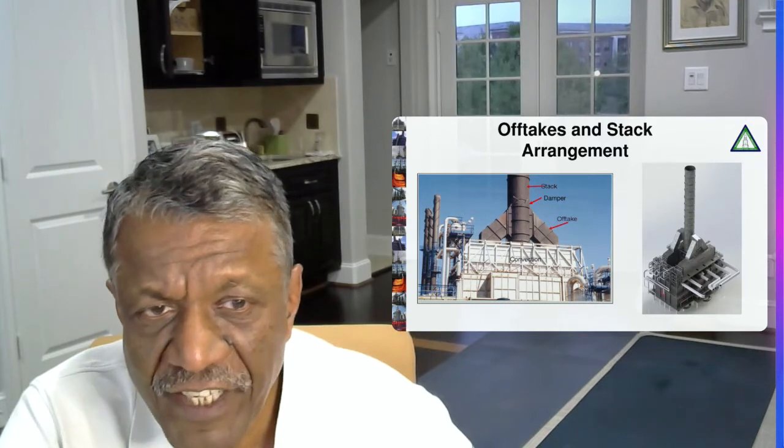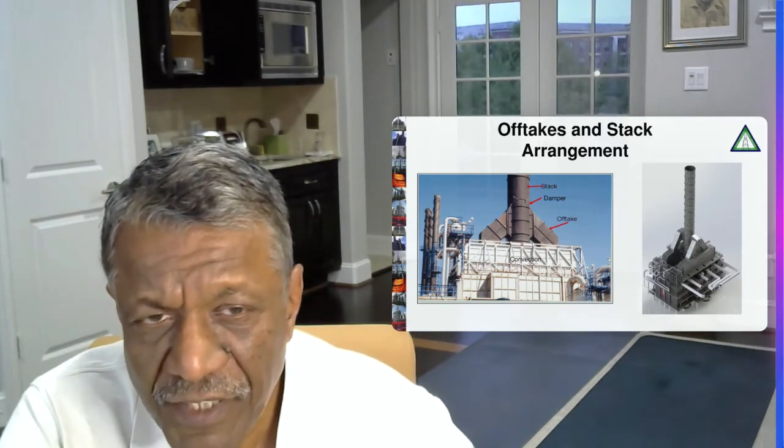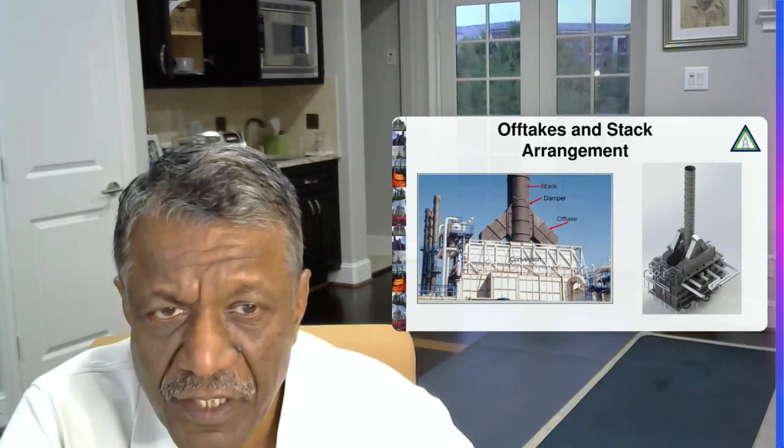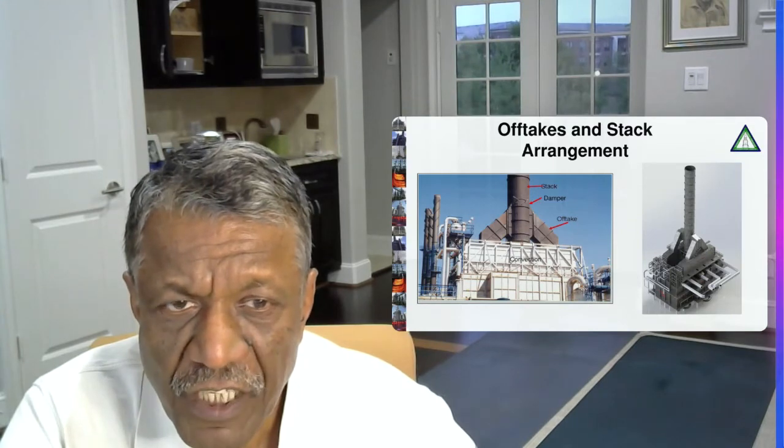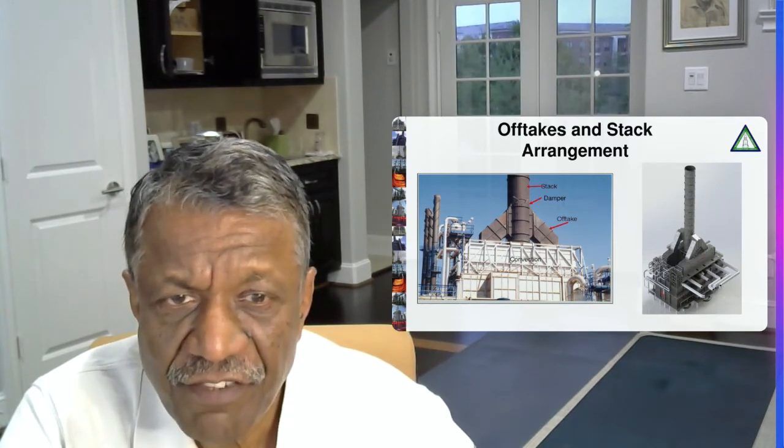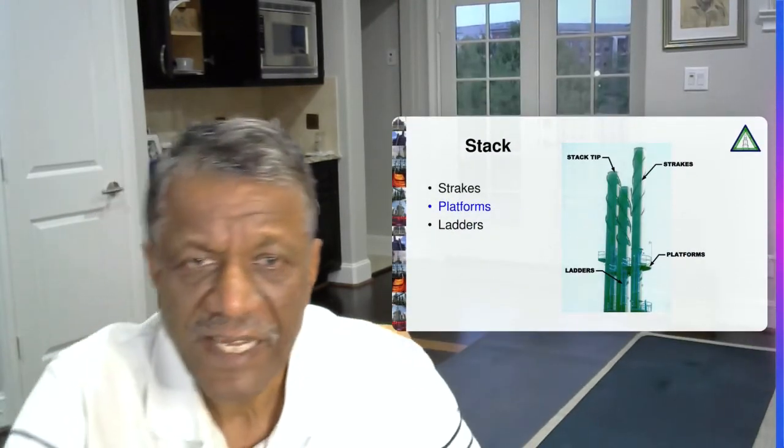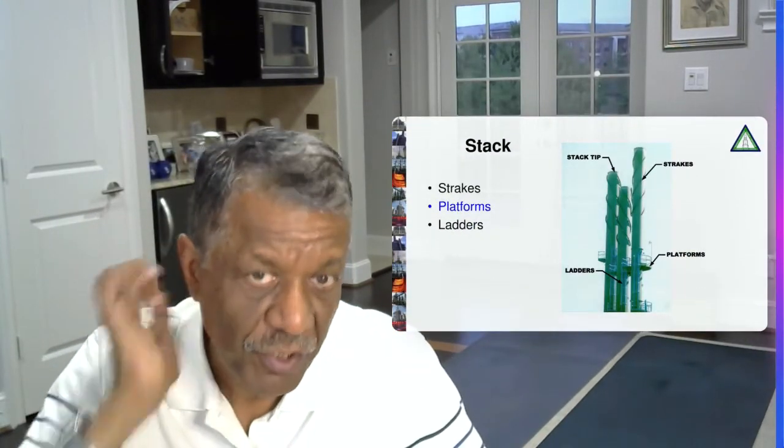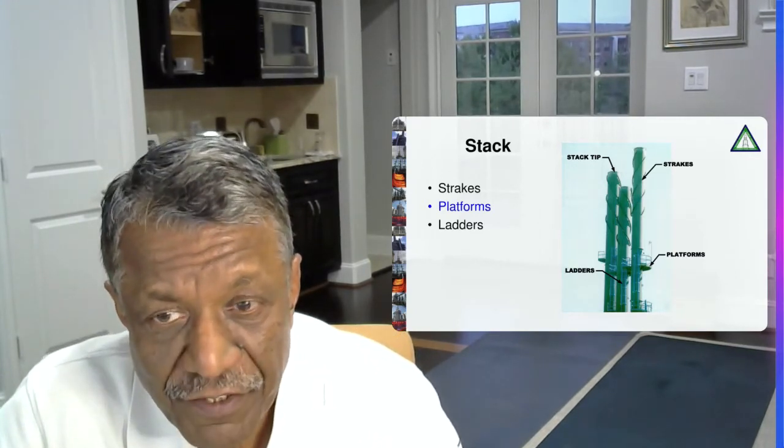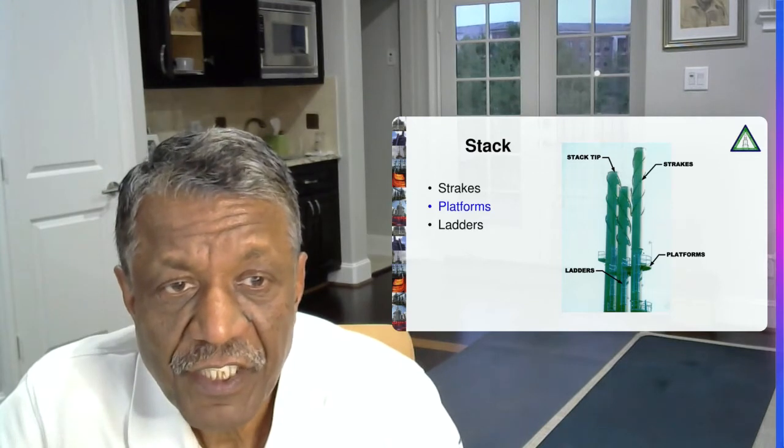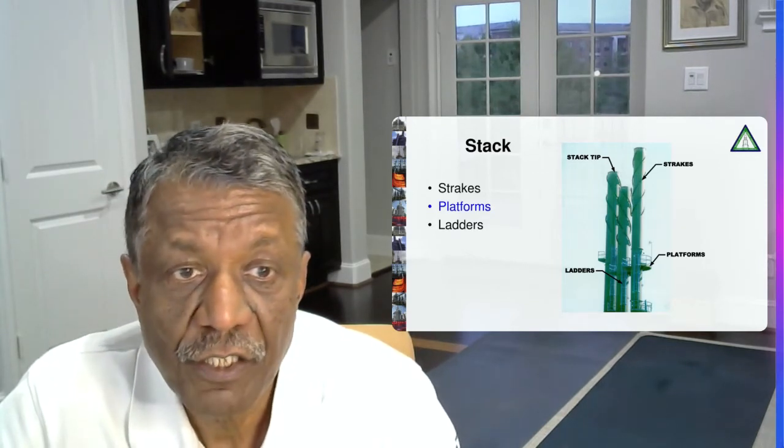Once the heat is recovered, we have the cold flue gases and they need to be disposed in the stack. So we use off-take ducts to transfer the flue gases from the convection to the stack. You can see a damper. A damper is like a butterfly valve which controls the draft in the furnace. So stacks are again a very important component. Their primary function is to dispose the flue gases. The secondary function is to create a draft in the fire heater, so they are basically dual function.